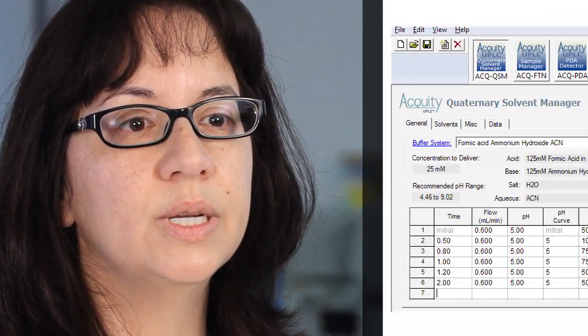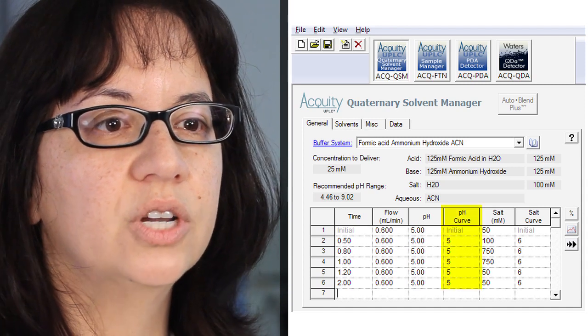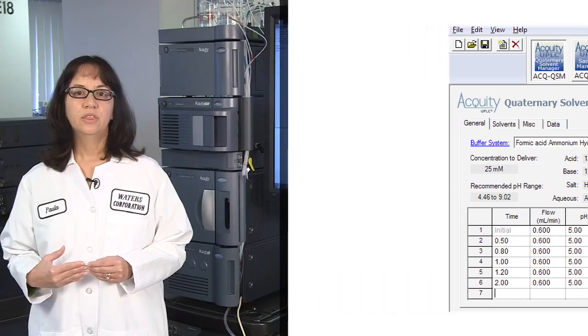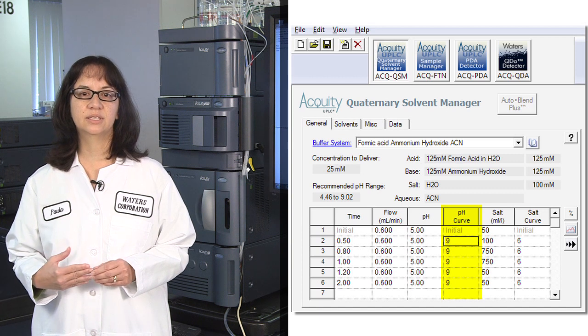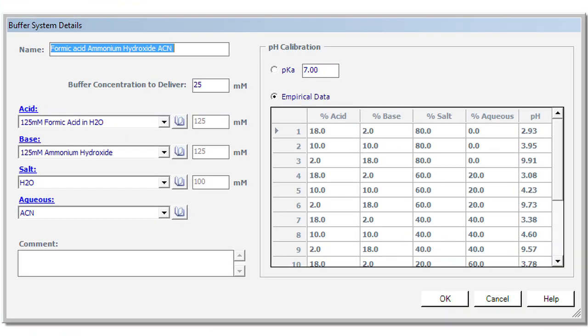As you can see here, the instrument method does not contain percentages but permits direct entry of the desired pH. You can program different methods at different pHs without making new buffers or changing bottles. The software algorithm calculates how to deliver the required pH based on the definition of a buffer system — that can include the pKa for the selected buffer or it can be based on an empirical table. The empirical table essentially calibrates the AutoBlendPlus with any pair of buffer components useful for the separation. We are using this flexibility to create buffer systems and mixtures of buffers that cover wide pH ranges and that are compatible with a variety of detection systems.